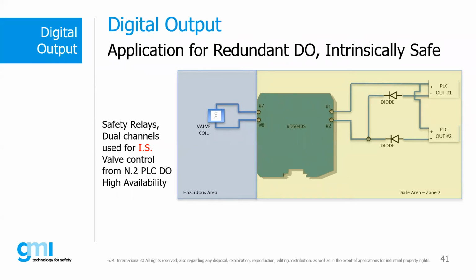The simplest and most cost-effective way is the one proposed in the slide, where redundancy is obtained up to the digital output card of the PLC. After that, through two diodes, we mix the common signal coming from the two diodes at the input of a single barrier that drives our final element. This is the simplest system, as by not performing operations that add a current in the hazardous area, there is no problem in terms of compatibility with the final elements, and moreover, it's certainly the most cost-effective solution, as the redundancy of the devices reaches the PLC only.